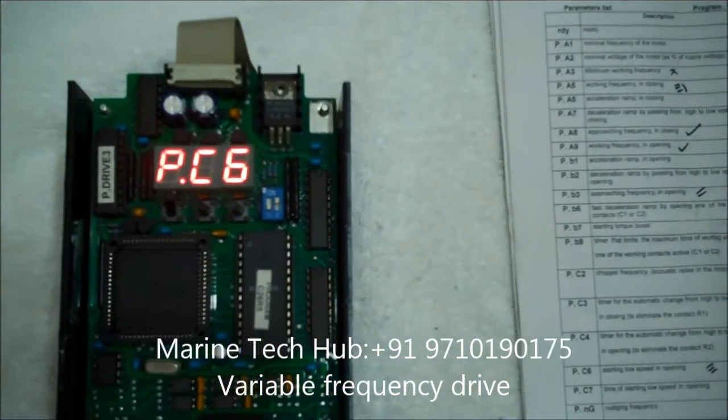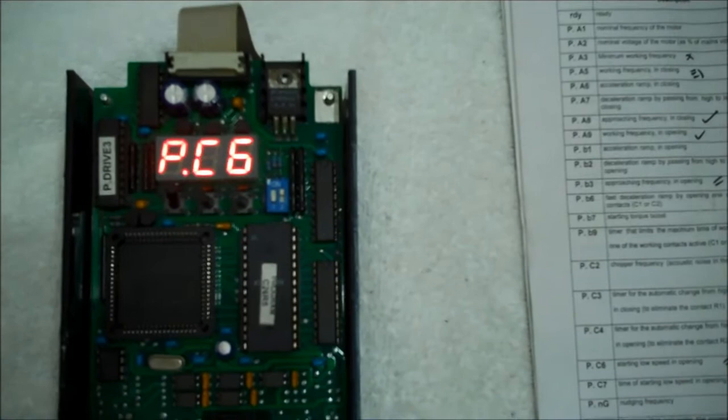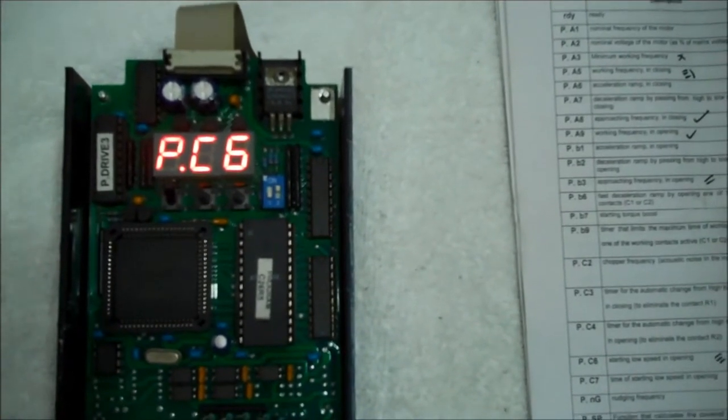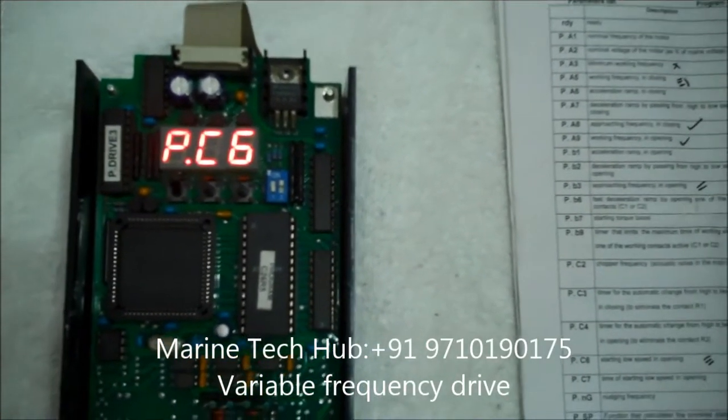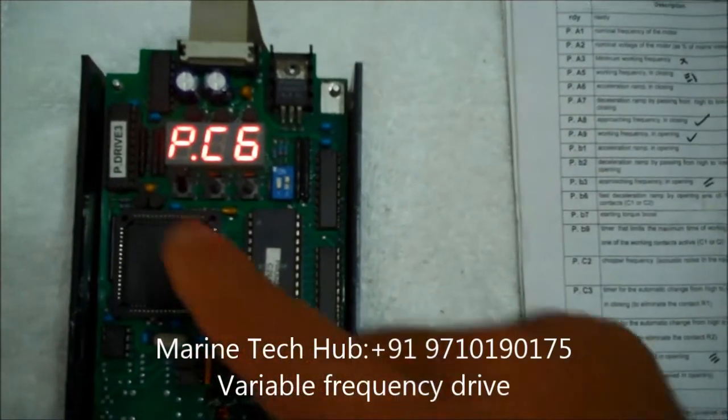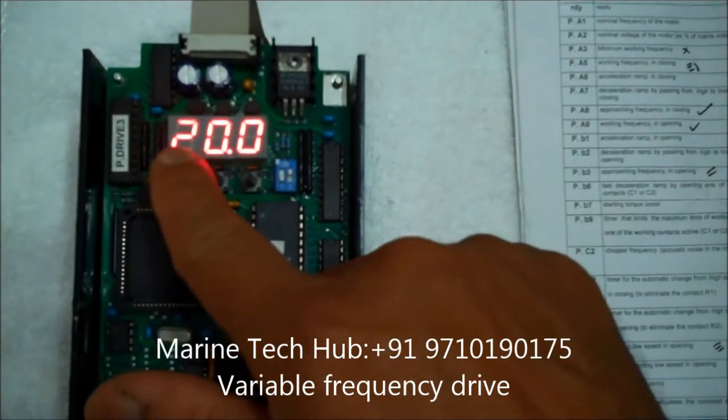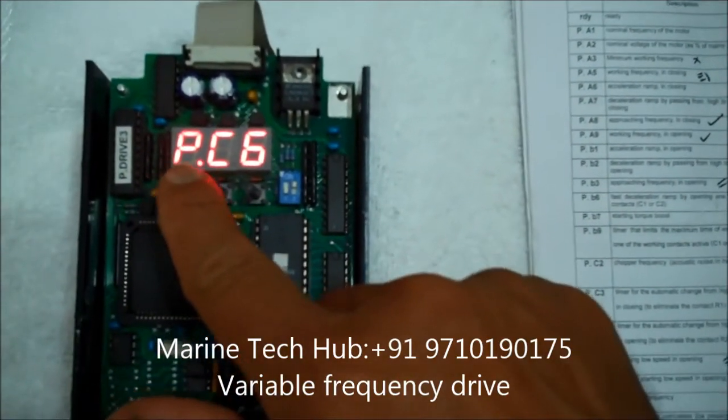Next is PC6. PC6 is the starting low speed in opening. This is normally kept say 20, 25 hertz. So let us see how much it is. 20 hertz. It is okay.